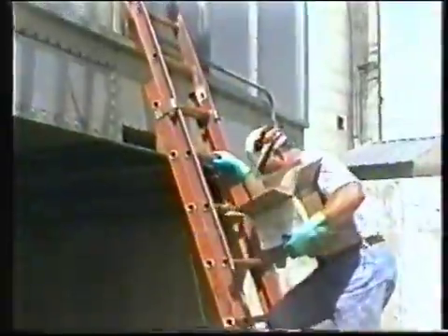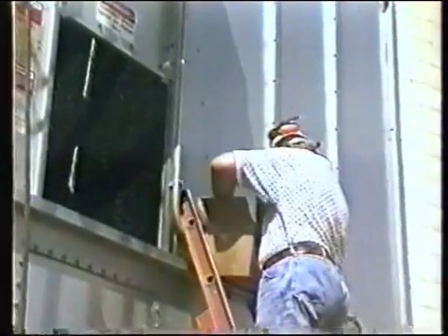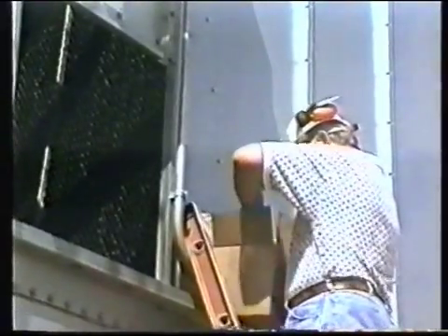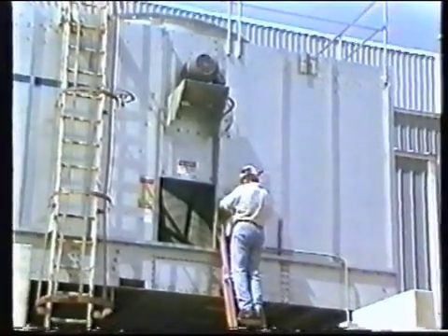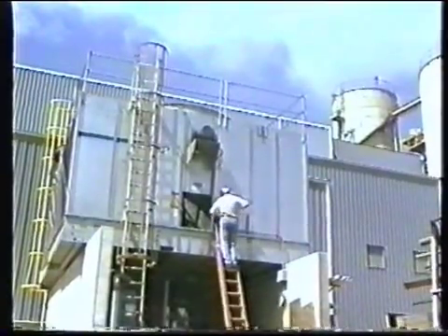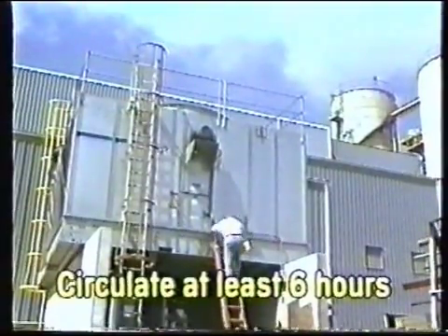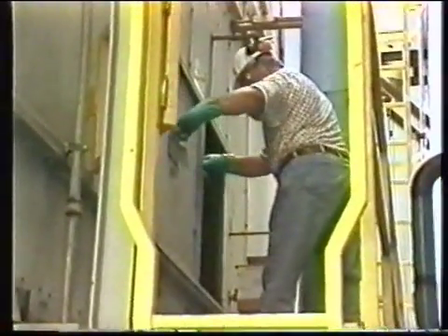Protects All 629P Cooling Tower Frogs use the water-soluble bag technique for laying up cooling systems, providing a convenient hands-off means of application. Each Cooling Tower Frog weighs only 2.2 pounds and can protect up to 250 gallons of water. Frogs are packaged 4 per carton to protect up to 1,000 gallons of system volume. To apply, simply toss directly into the cooling tower and circulate. Depending on water temperature, the water-soluble bag will dissolve within 15 minutes. Circulate for at least six hours to reach all piping and equipment.